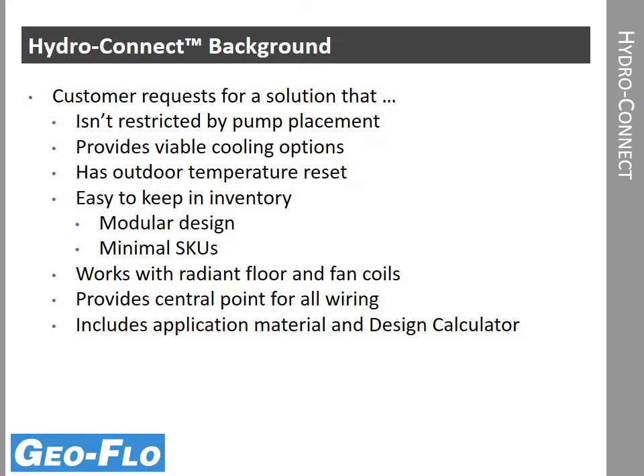We want to make sure that the system can work with both radiant floor and fan coil systems. That was one of the design criteria. Providing a central point for all wiring makes installation easier, and it's much easier also later on to troubleshoot the system. The new system includes application material that is pretty comprehensive, as well as a calculator that's online for buffer tank sizing.